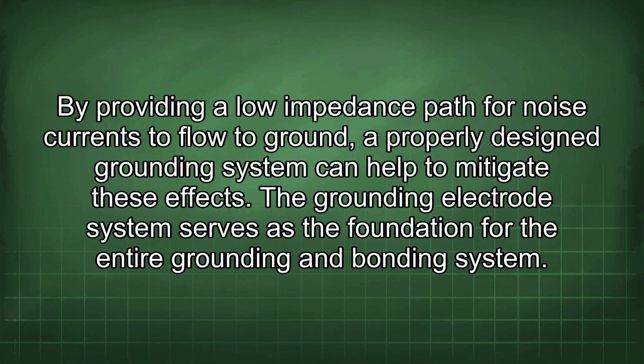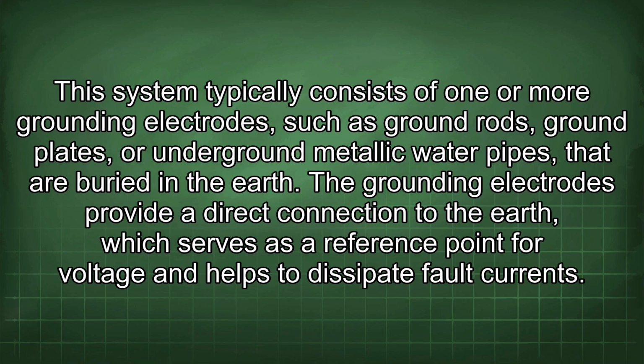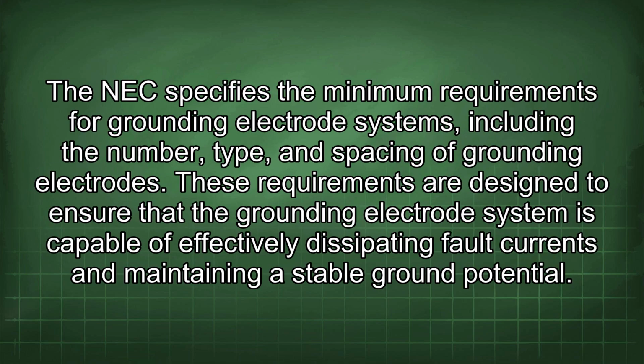The grounding electrode system serves as the foundation for the entire grounding and bonding system. This system typically consists of one or more grounding electrodes, such as ground rods, ground plates, or underground metallic water pipes that are buried in the earth. The grounding electrodes provide a direct connection to the earth, which serves as a reference point for voltage and helps to dissipate fault currents. The NEC specifies the minimum requirements for grounding electrode systems, including the number, type, and spacing of grounding electrodes. These requirements are designed to ensure that the grounding electrode system is capable of effectively dissipating fault currents and maintaining a stable ground potential.